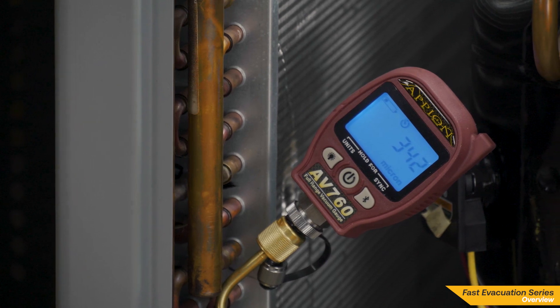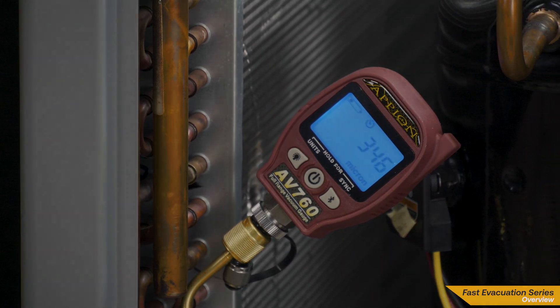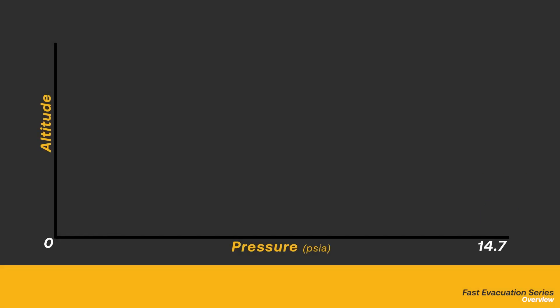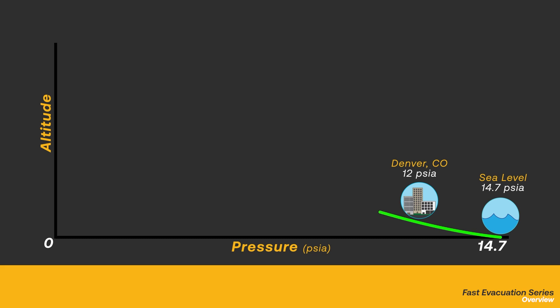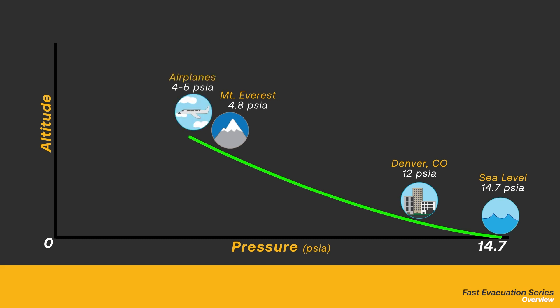To start, we should take a moment to understand what vacuum is. At sea level, atmospheric pressure is 14.7 psia, or absolute, created by the gravitational effect on the Earth's atmosphere. Atmospheric pressure will reduce as altitude increases. Sometimes vacuum is described as a negative pressure, which isn't entirely true. Vacuum is still a positive pressure above 0 psia, but because it is below atmospheric pressure, we conceive it as a negative pressure.